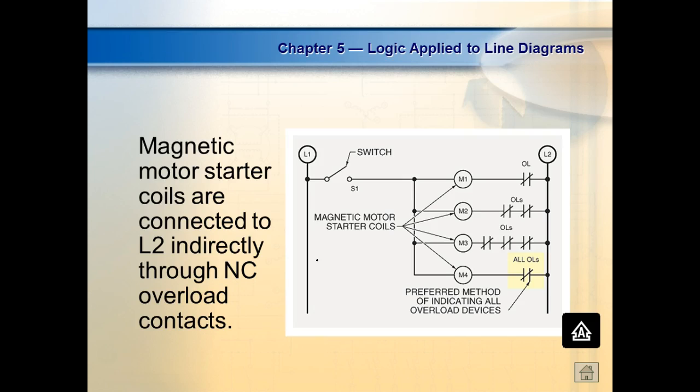So if you put an overload, then you have a motor starter. Not only a motor, it's got to be a motor that doesn't have an internal overload. So for a motor that doesn't have an internal overload, we have to put the overloads outside, right? You understand that? And that's where these guys will come into play.